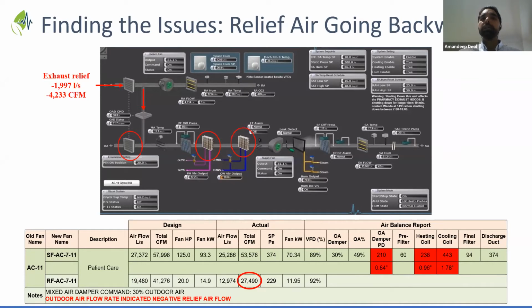So the air sees the least path resistance is through the relief duct rather than through the outside air damper. So the system is making up that air through that relief duct rather than through the outside air damper. This leads to additional problems, and you're not able to maintain your system or pressurization in the building because these fundamental issues within the system haven't been resolved.